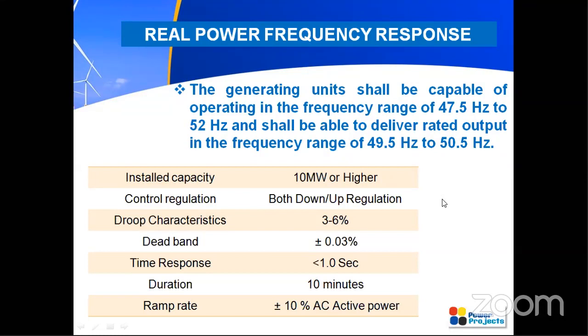If it is a generating station of aggregate capacity, for example, if you have 10 wind farms and the aggregate capacity is 500 megawatt, and you are integrating it with the grid, they can have a provision to receive the signal from the state load dispatch center or regional load dispatch center. Accordingly they can vary their active and reactive power output. But all these are for installed capacity. This condition is especially for an installed capacity of 10 megawatt and an operating voltage range of 33 kV and above. The wind farms with installed capacity of 10 megawatt and higher, operating at 33 kV and higher, have to follow all these conditions of real power frequency response.